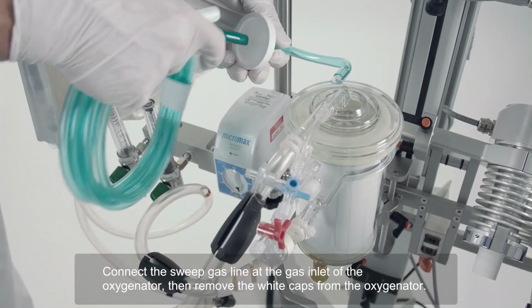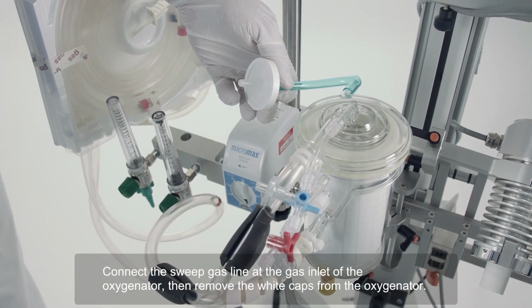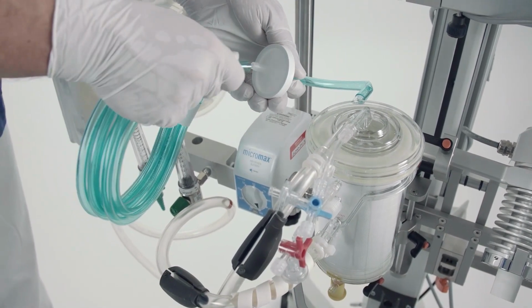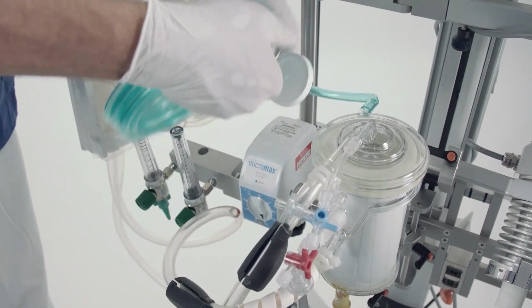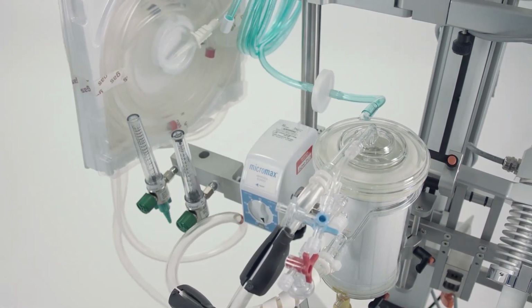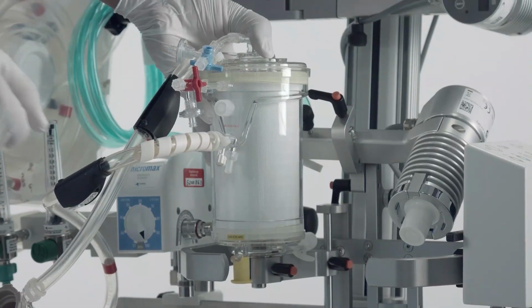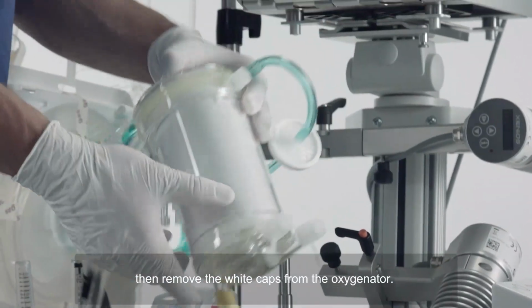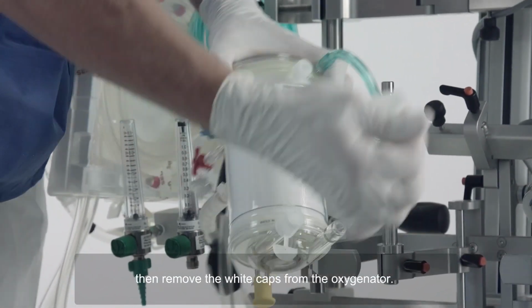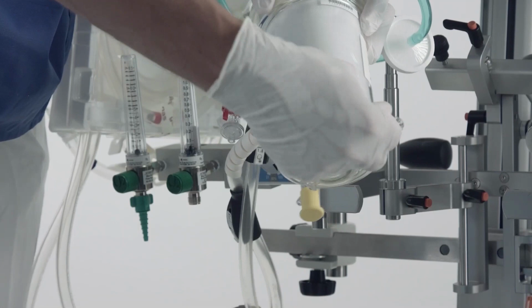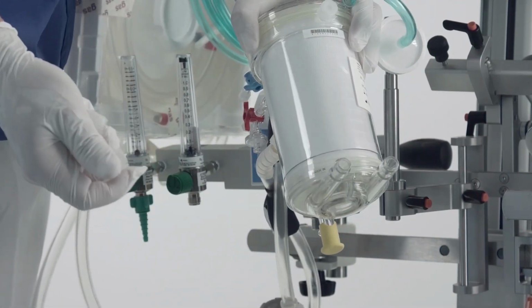Connect the sweep gas line at the gas inlet of the oxygenator. Then remove the white caps from the oxygenator. Now prepare the HC unit. Therefore, please also consult the corresponding IFU. First, de-air the HC unit. Then connect the water hoses of the HC unit to the water inlet and water outlet connector of the oxygenator.